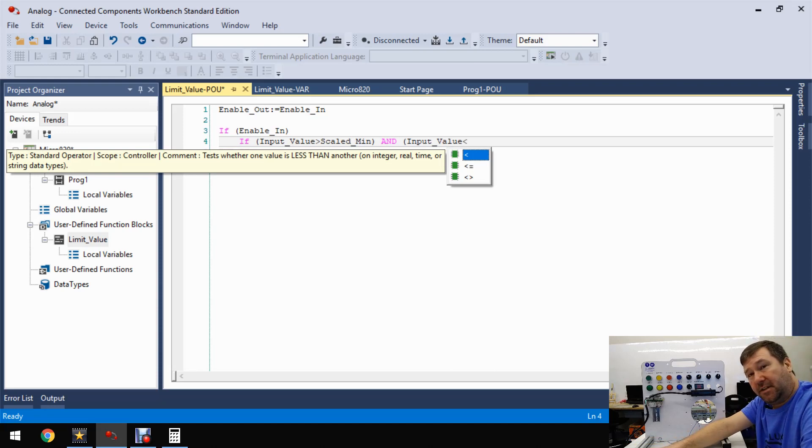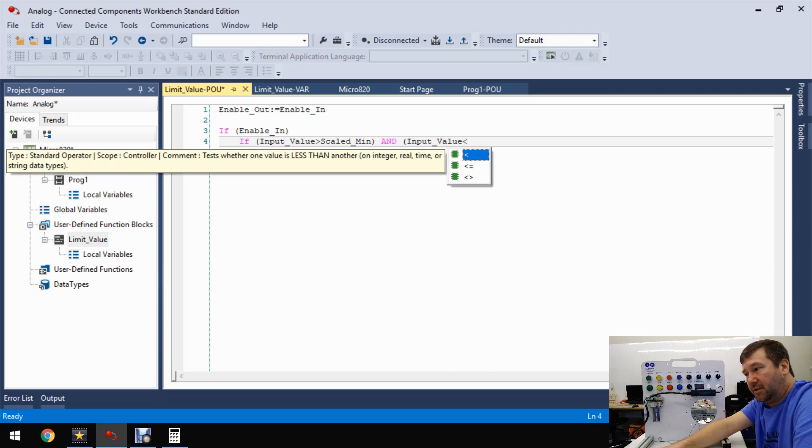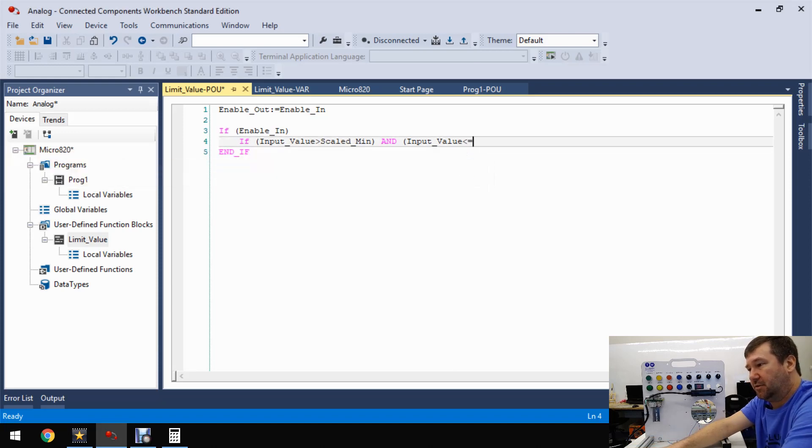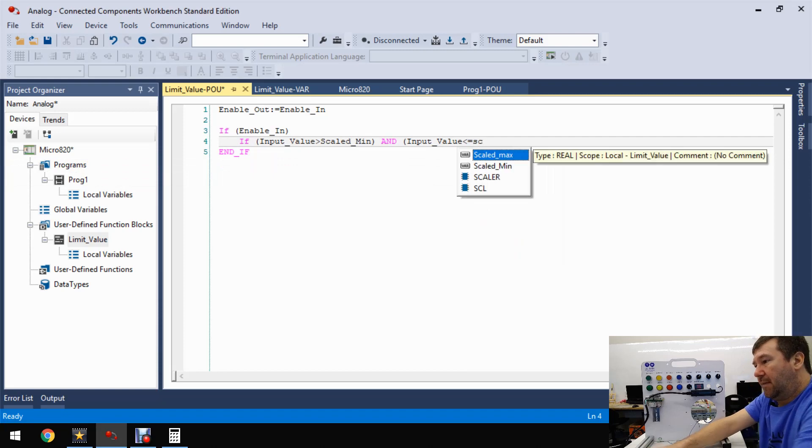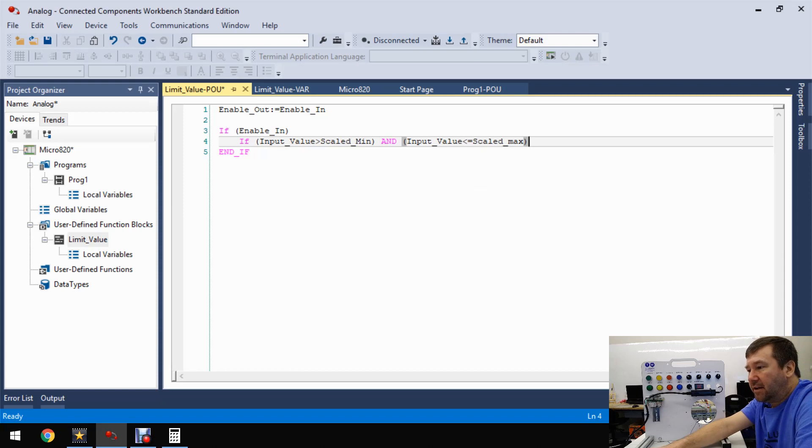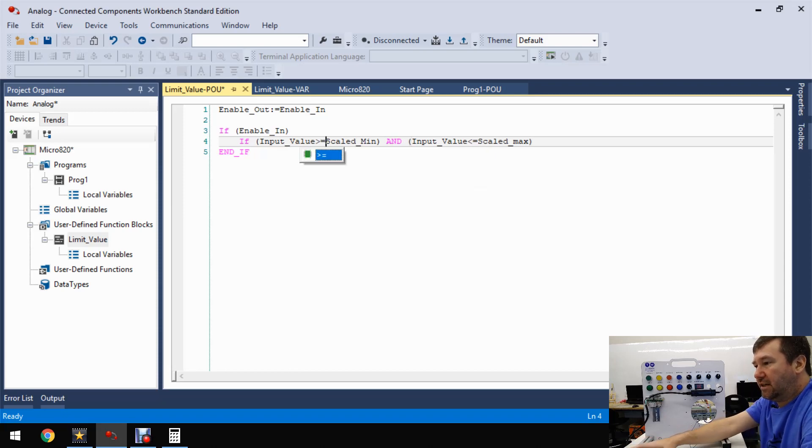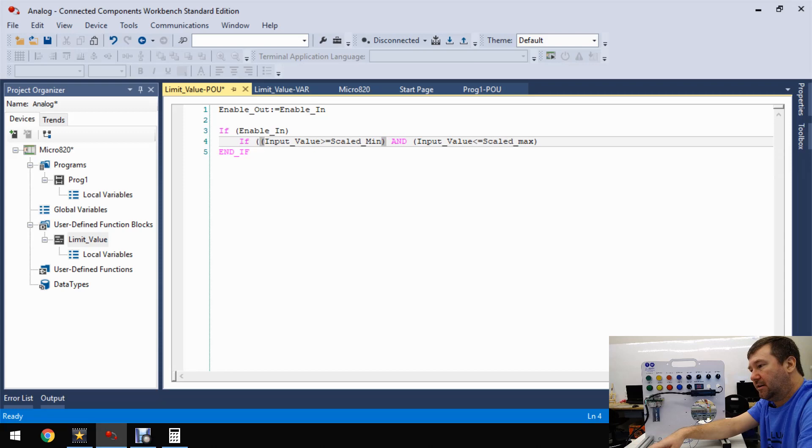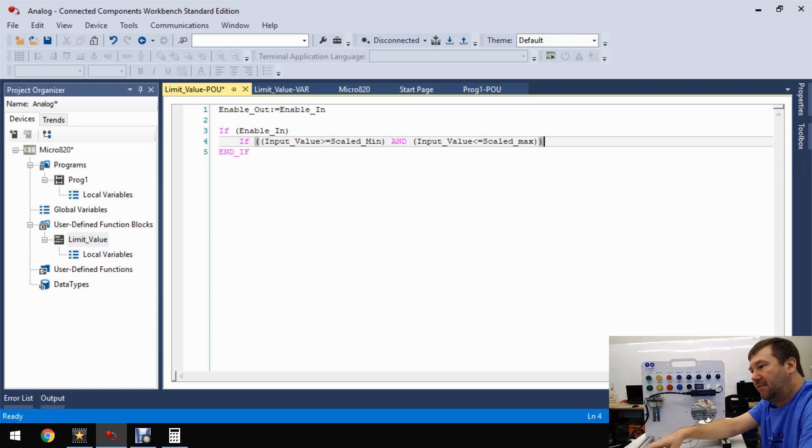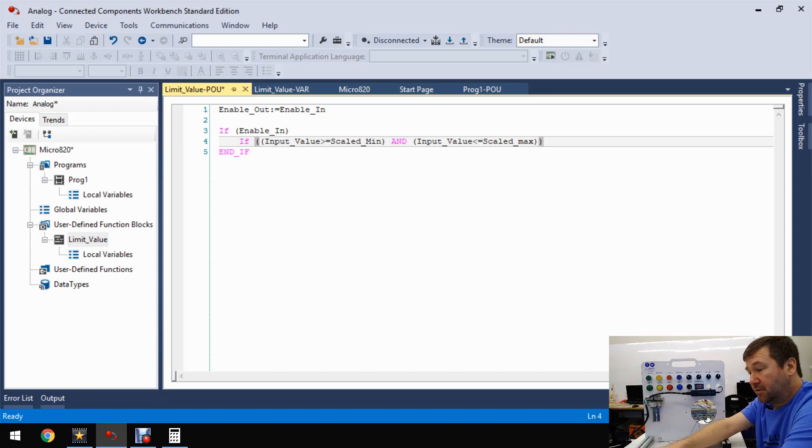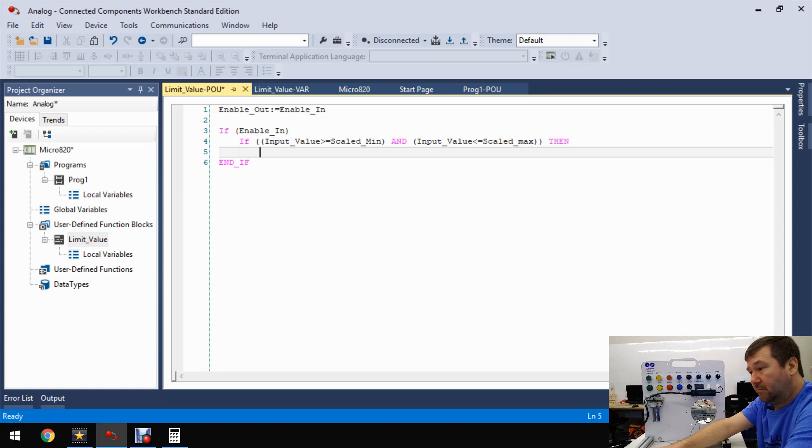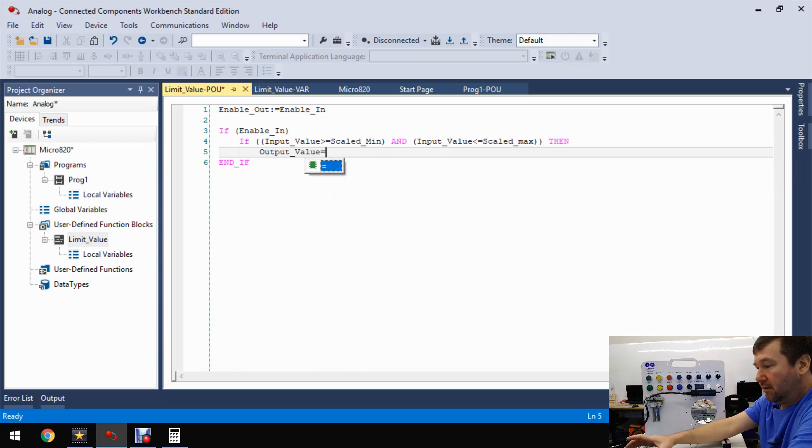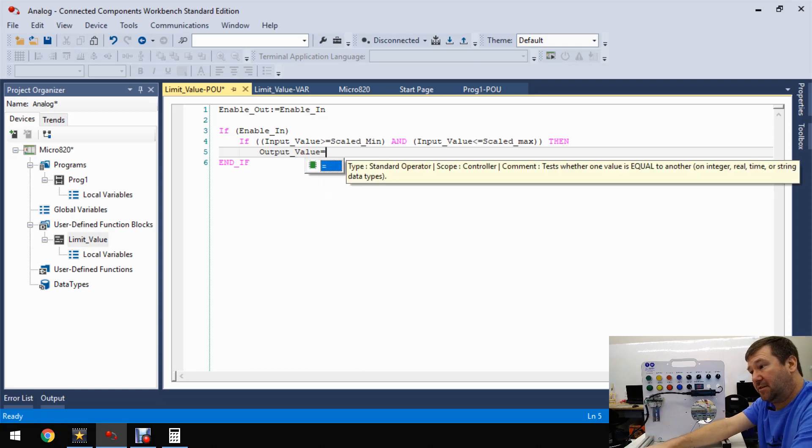Then we're going to type another if. We have three conditions that we need to do if-thens for - either our value is going to be within the range of our min and max, and we can shoot that on through, or our value is going to be too high, which means that if we're at 21 milliamp, we're going to need to put 20 in it, or our range is too low. So let's say we're at 2 milliamp, we'll need to put that 4 in it. We're going to be looking at our input value. And first, if it is greater than - and this will be our minimum value, it's a scaled minimum - and then close parentheses - I just realized I made a mistake on the first one, that should have been greater than or equal to. We'll fix that first one in just a second.